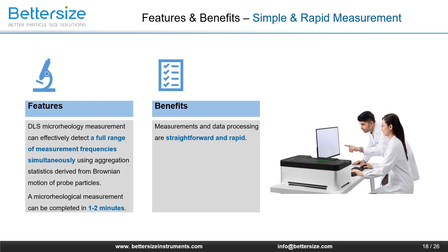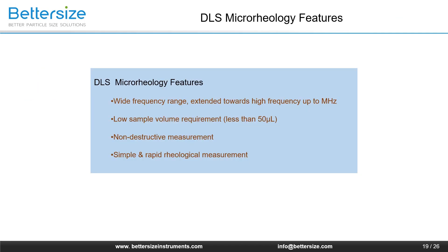B-nano series microrheology measurements are performed in 1 to 2 minutes, making both the measurement and data processing simple and fast. In summary, the features and benefits of DLS microrheology include: wide frequency range extended to high frequencies up to megahertz, small sample volume requirement of less than 50 microliters, non-destructive measurement, and simple and rapid rheology measurement.